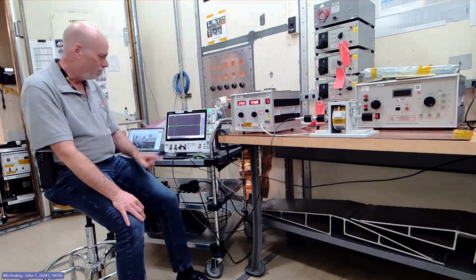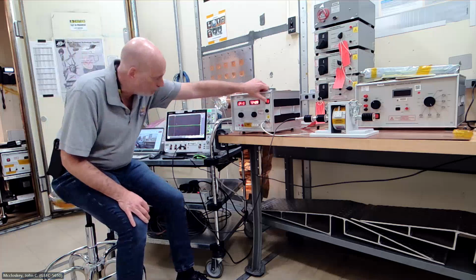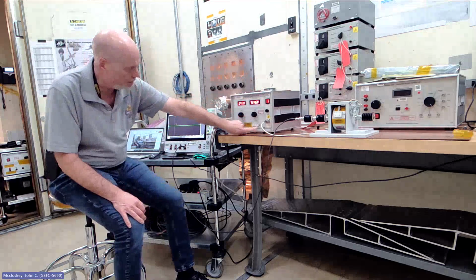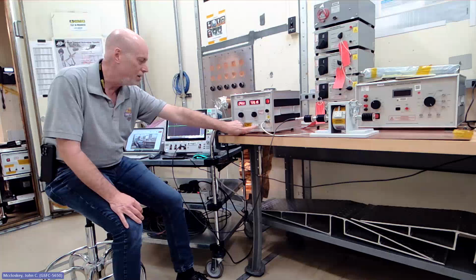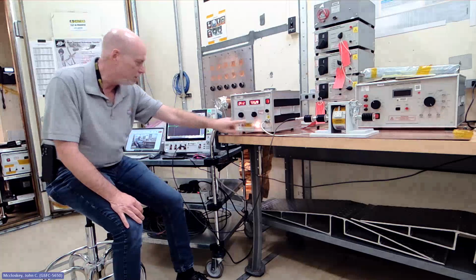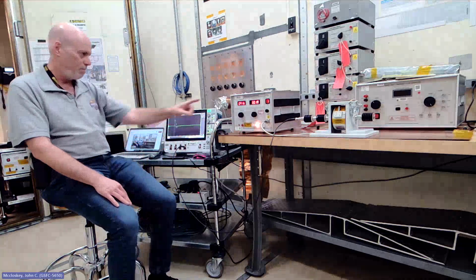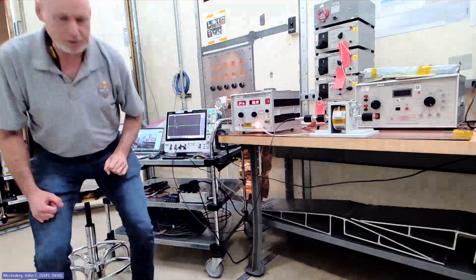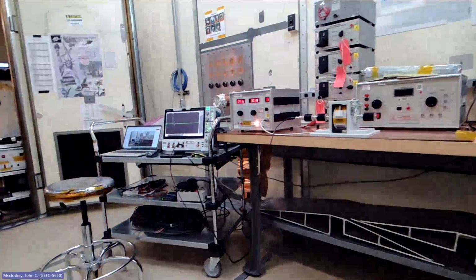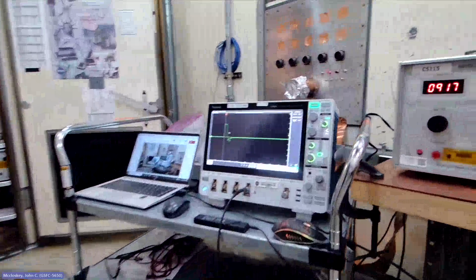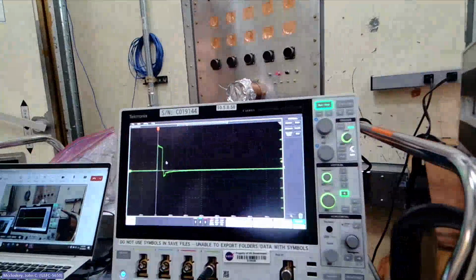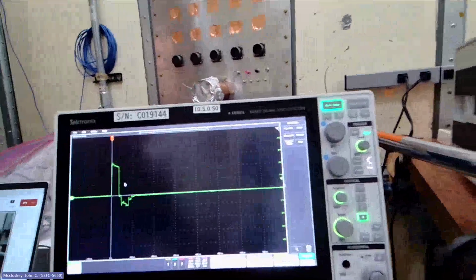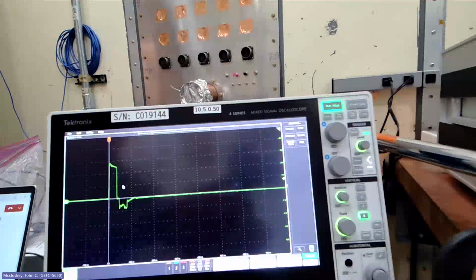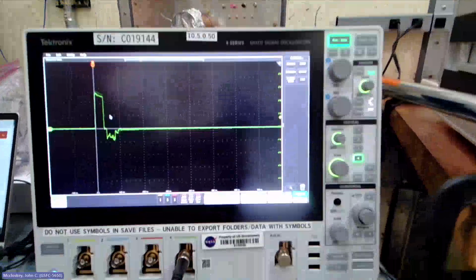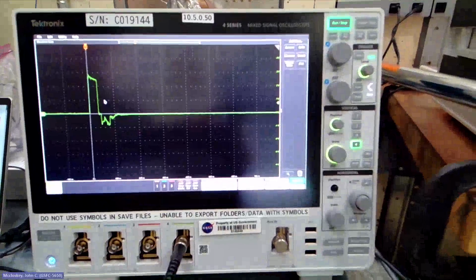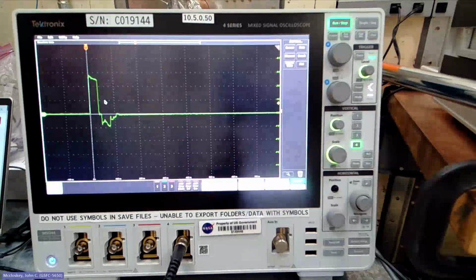So I'm now going to turn on the signal generator. It's already on, it's just the output is disabled. So we're going to turn this on and we're going to have about 30 pulses per second for the spec. I'm going to bring the camera over here so you can see the scope. You can see the signal characteristics. And I'm injecting the full 5 amps per the requirement. We sometimes tailor the limit down to 1 amp, but I'm injecting the full 5 amps.